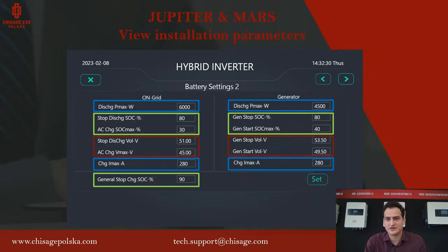On the second page, we have the on-grid and generator settings: how the battery is working in on-grid mode and how the battery is working with the genset. The blue frames we fill all the time, so discharge power maximum and charging current maximum we have to fill. And then we pick green or red frames, depending. If we use lithium, we fill the percentage. The red frames we fill if we use battery voltage.